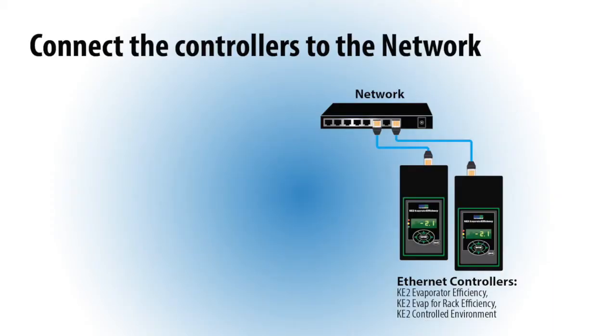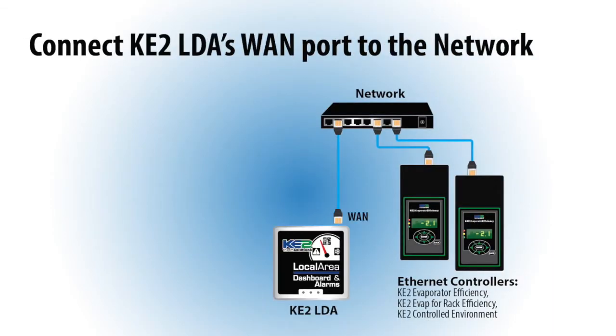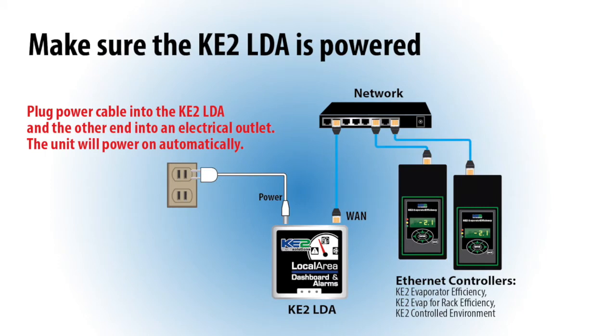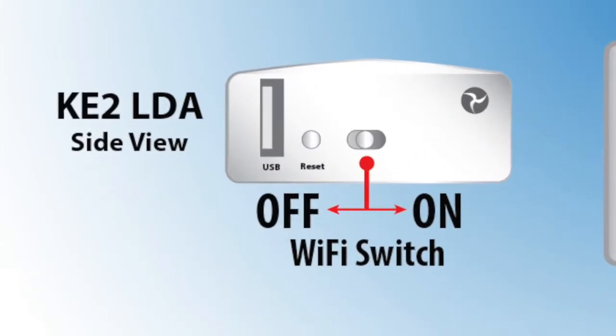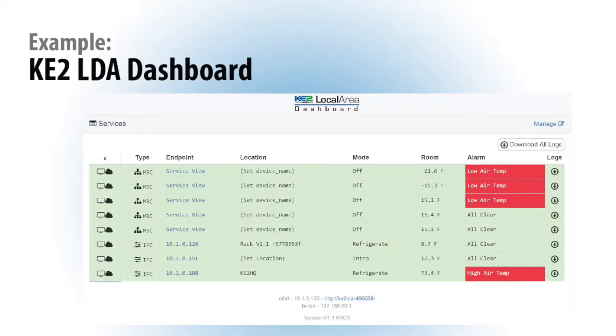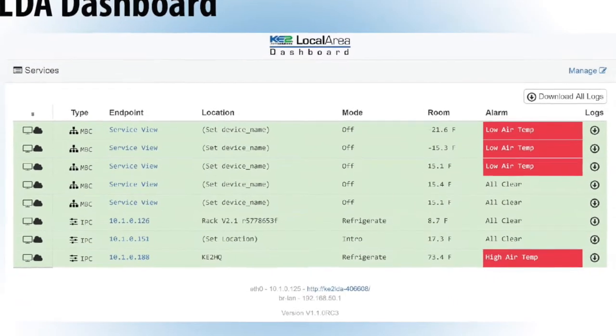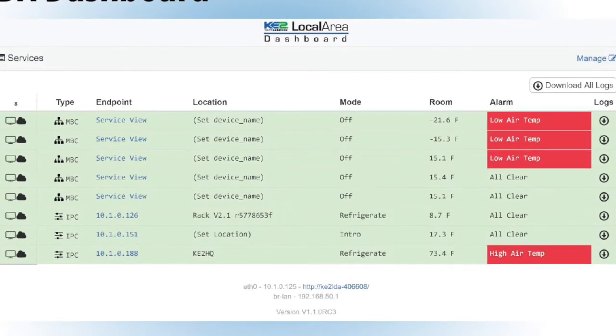First, you'll need to connect the controllers to the customer network. Then connect from the KE2 LDA's WAN port to the customer network. Make sure the KE2 LDA is plugged in and the wireless switch is moved to ON. The KE2 LDA will automatically find the KE2 Therm controllers connected to the local network and display them on the dashboard.